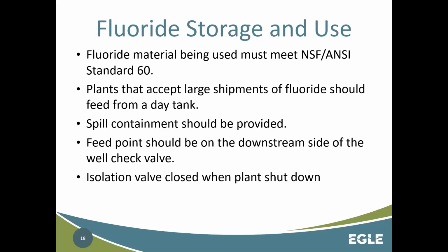Spill containment should be provided. Any feed points should be on the downstream side of a well check valve. And you should be able to isolate the fluoride feed when the plant is shut down.